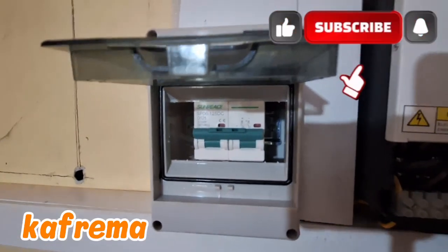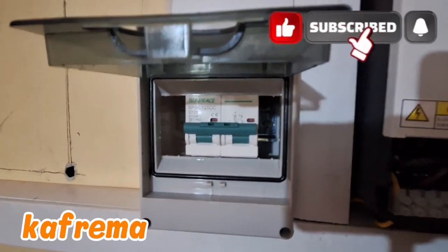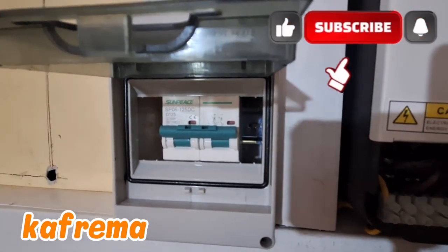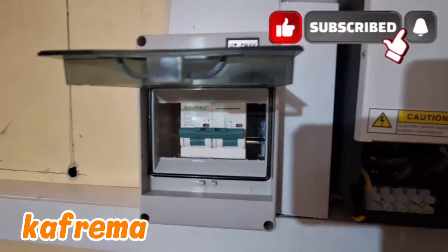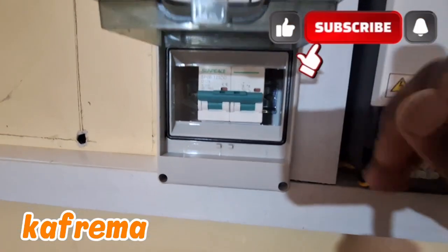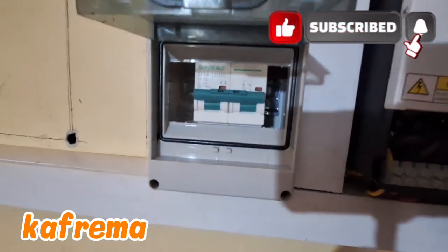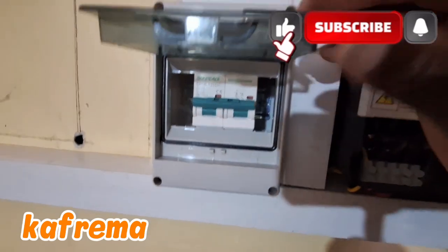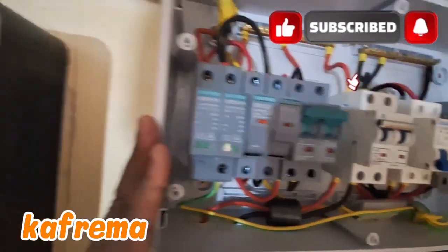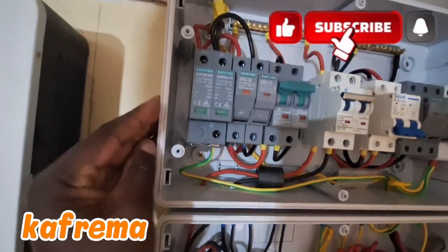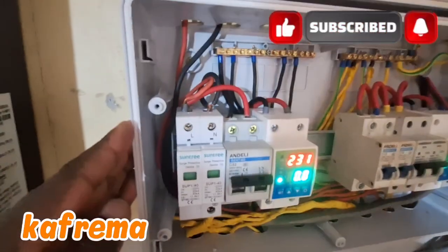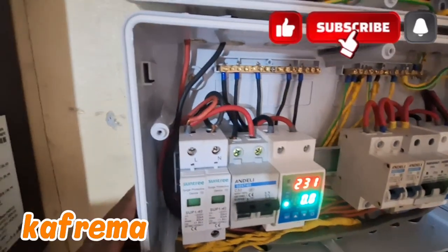So if our inverter draws more than 3000 watts or more than 125 amperes, this one will trip. That is protecting our inverter and also the battery bank. That's one of the protections for our inverter. The others are in these two boxes. Here is the DC box, and this is the AC box. It is important to separate the two.